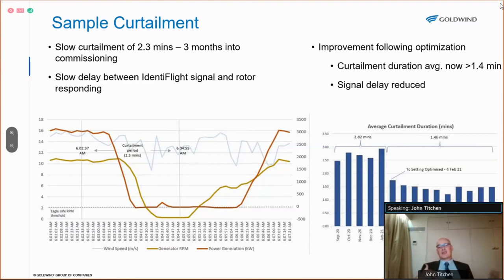We also had a fairly slow signal between the IdentiFlight triggering a risk and the turbine rotor slowing. You can see on the right here that these columns are the duration of the shutdowns. We made some setting changes in February this year and were able to almost halve the duration of shutdowns, to around 1.4 minutes.